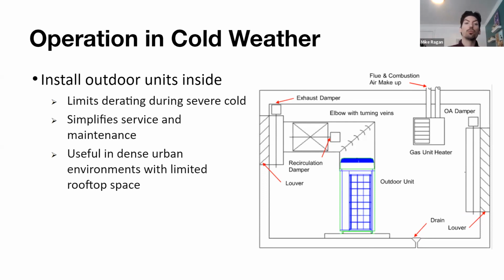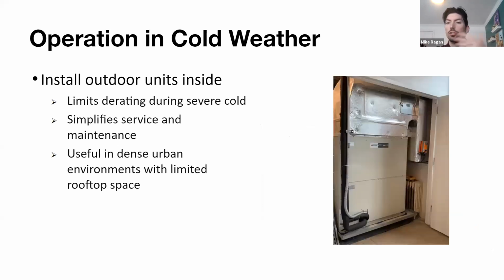This particular configuration greatly simplifies service and maintenance. Your contractor is going to be thanking you if he has the luxury of working in a covered, heated space in the dead of winter. And this is also a very useful tactic if you're working in urban environments, high-rise environments where there's very limited rooftop space. You can actually put this equipment indoors through louvered walls on the side of a building and potentially have your condensing unit module on each floor. So this way you're not utilizing your rooftop space. You're potentially freeing up rooftop space for PV solar arrays effectively. So here are just various considerations as well.